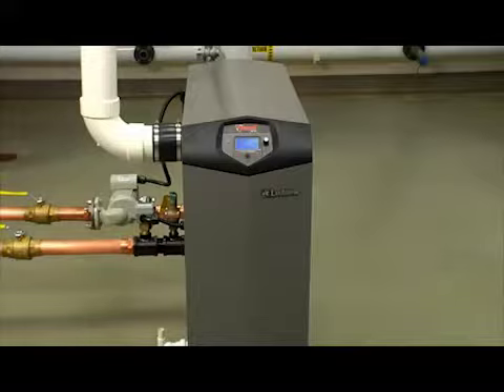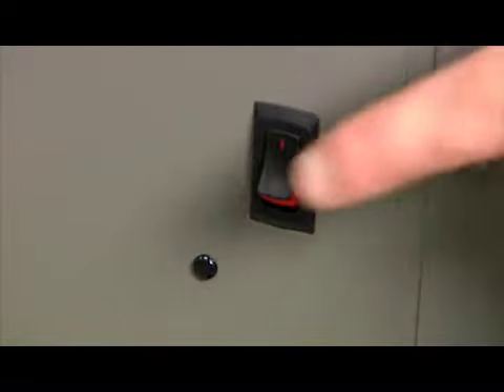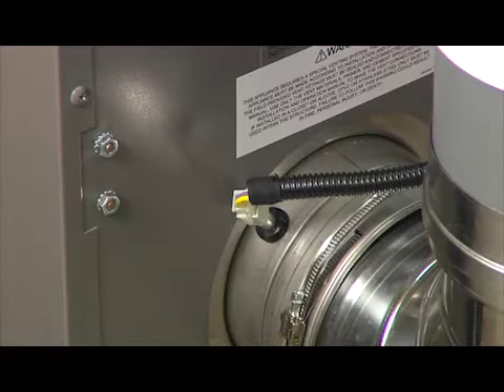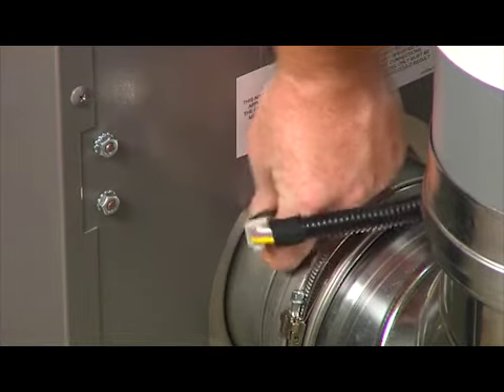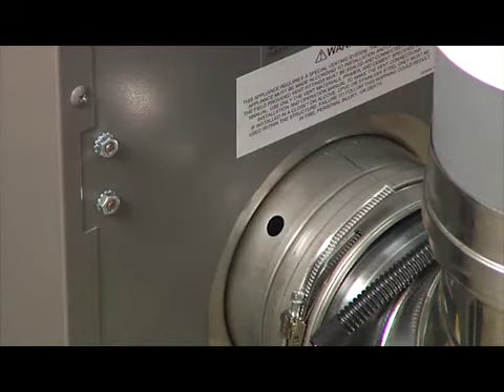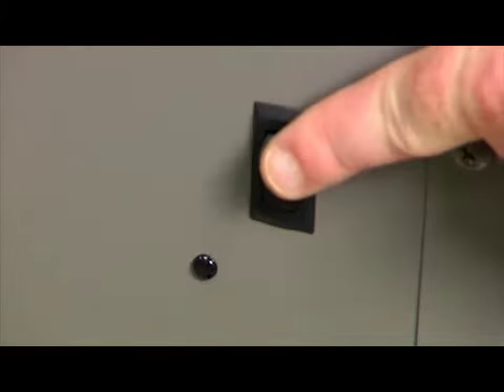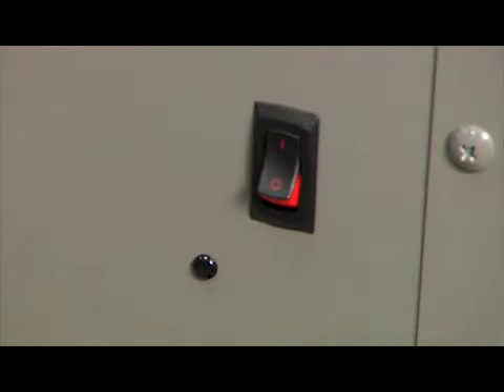Locate the on-off switch on the back of the unit. Turn the switch to the off position. Locate the flue sensor in the vent connection on the back of the unit. Remove the flue sensor and rubber grommet from the vent connection. Turn the on-off switch to the on position.